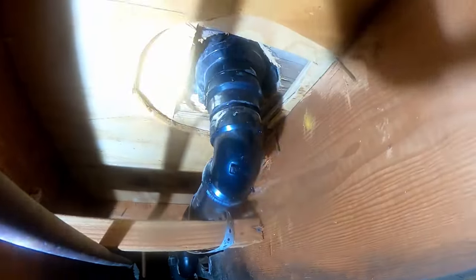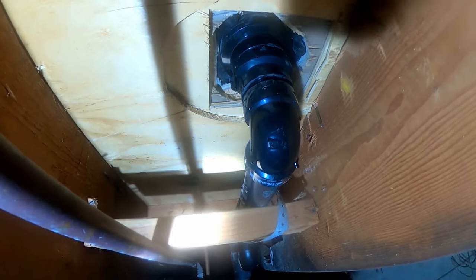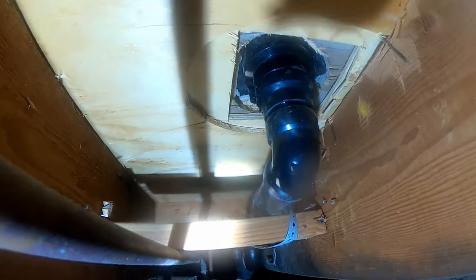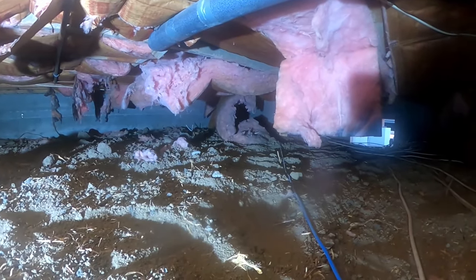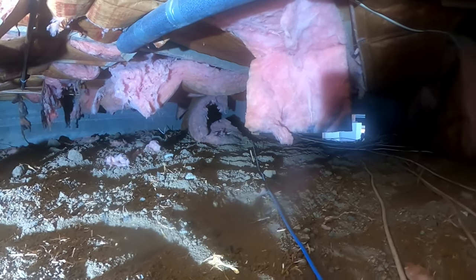Look at that right there — that's crazy. Who would plumb that like that? The shower should be two-inch pipe. It's inch-and-a-half. They plumbed it in like a tub. Absolutely ridiculous. We're still going to run the smoke because with plumbing like that, who knows what they did inside the wall and in the venting system.